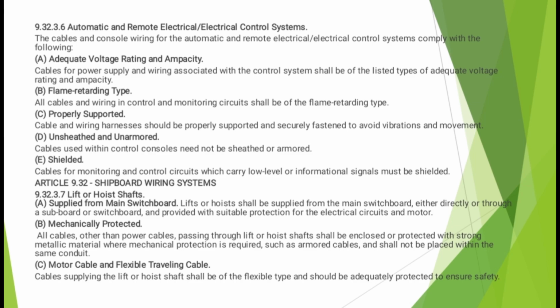Lift or hoist shaft. Supplied from main switchboard. Lift or hoist shaft shall be supplied from the main switchboard either directly or through a subboard or switchboard and provided with suitable protection for electrical circuits and motors. Mechanically protected. All cables other than power cables passing through lift or hoist shaft shall be enclosed or protected with strong metallic material where mechanical protection is required, such as armored cables, and shall not be placed within the same conduit. Motor cable and flexible traveling cable.